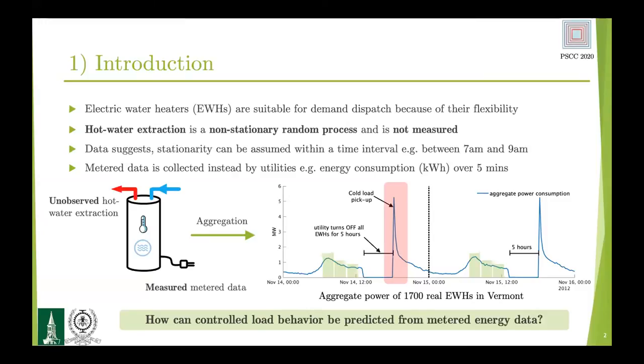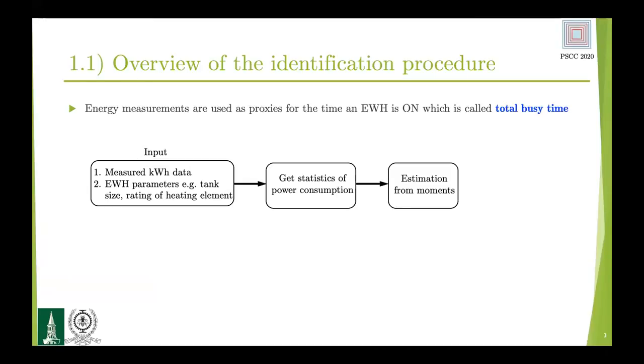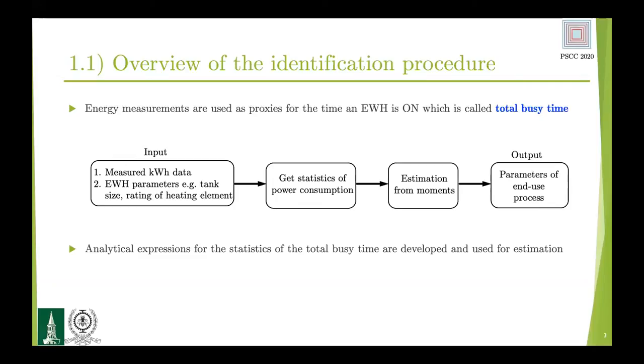Based on the limitation of the data available, we are really interested in the models of the end-use consumption that are identifiable from the AMI data. We take as input the AMI data and calculate what's called the total busy time, which represents the total time an electric water heater was on within a time period. The AMI data is collected in the form of kilowatt-hours within 15 minutes, for example, and total busy time represents what portion of that 15-minute interval the electric water heater was on. Along with some fleet information — like the rating of the heating element or thermal time constants — we compute statistics of this total busy time and feed them to our estimation algorithm to get as output the parameters of the end-use process. In this work, we develop first the analytical expressions of the statistics of total busy time, and then use them for estimation.